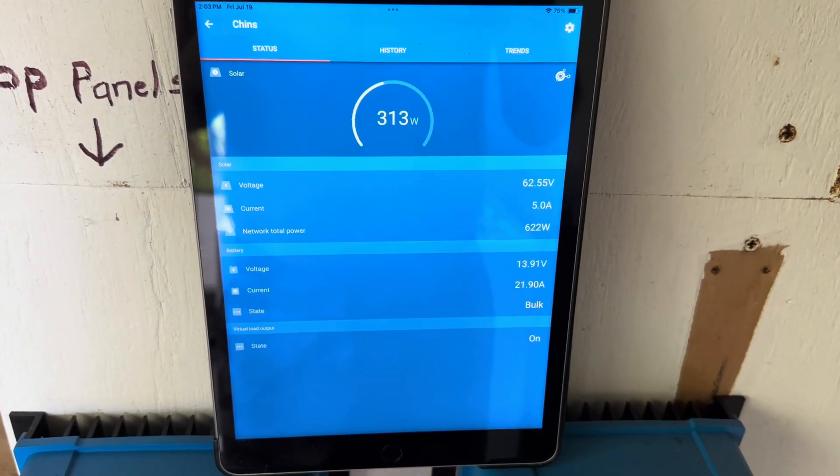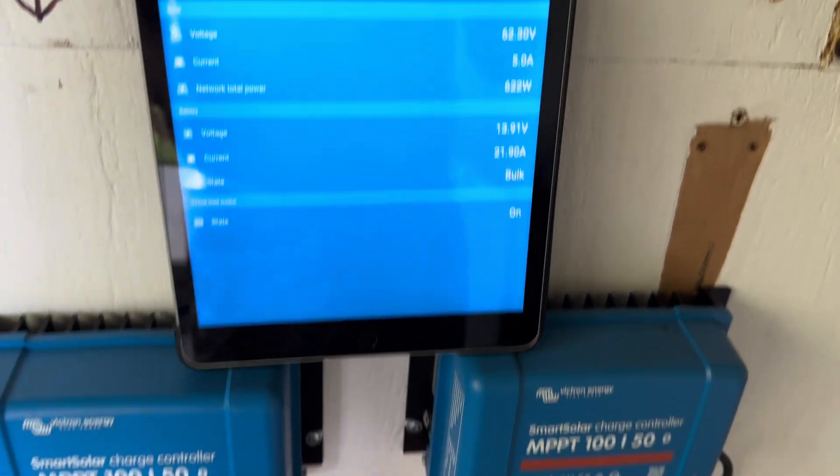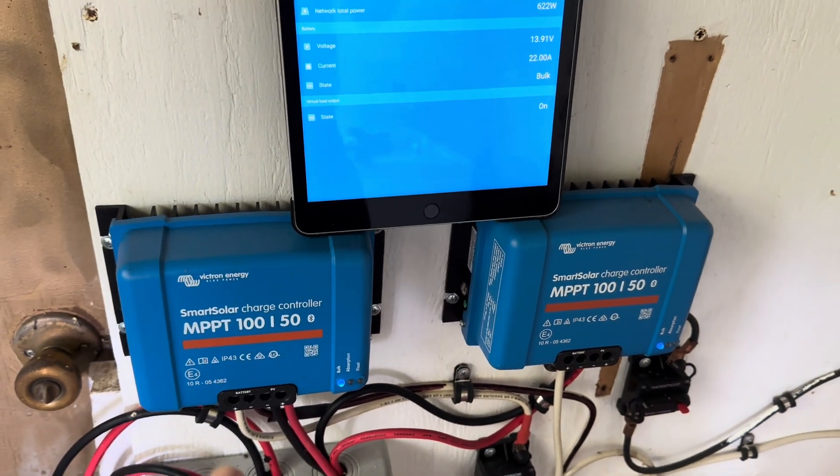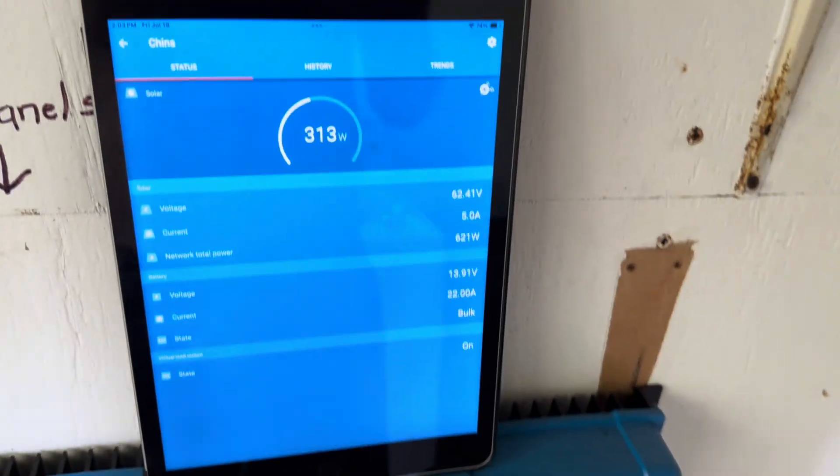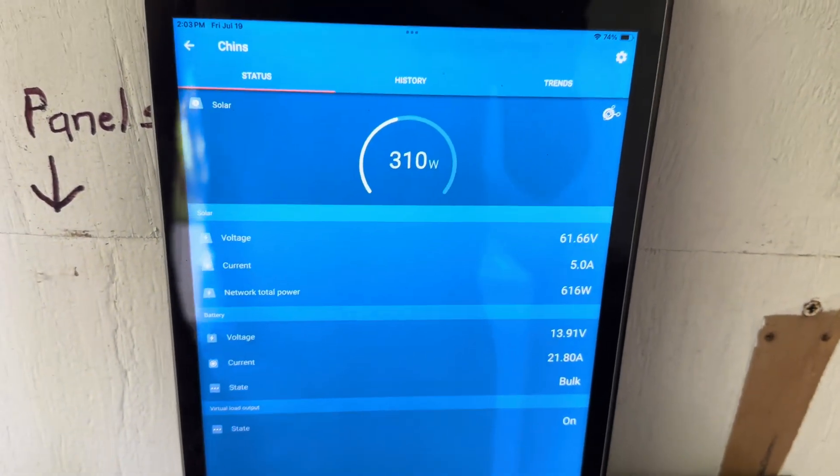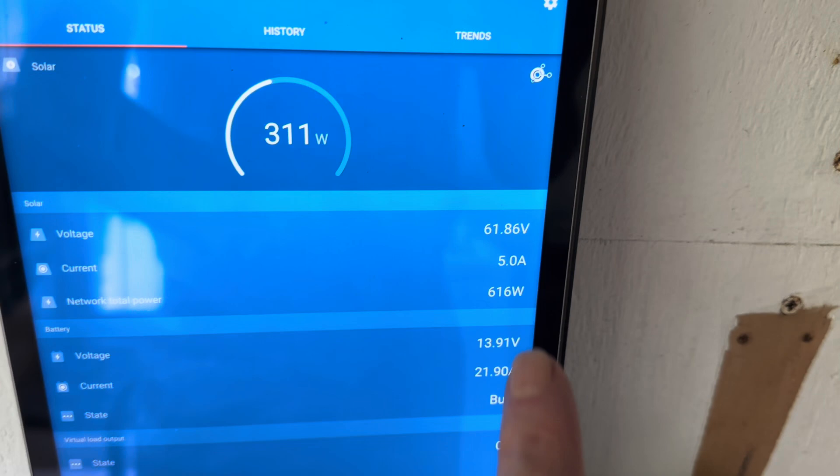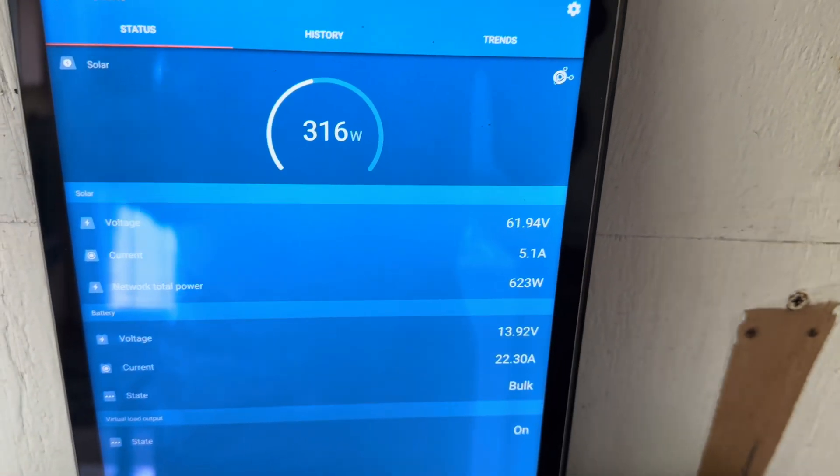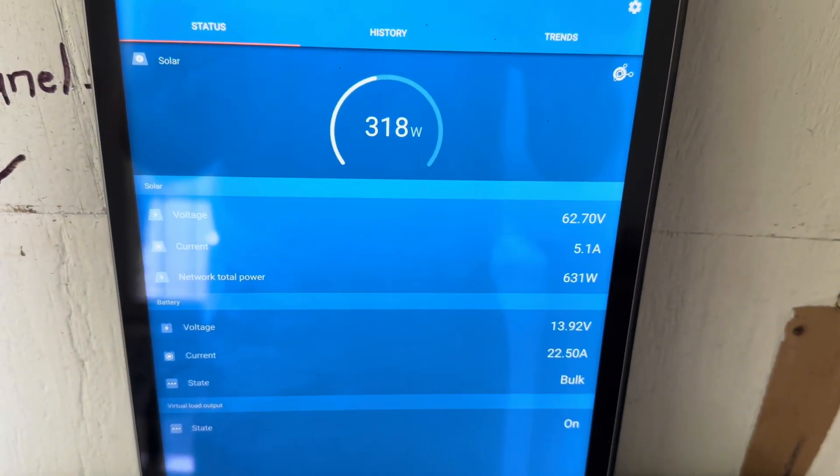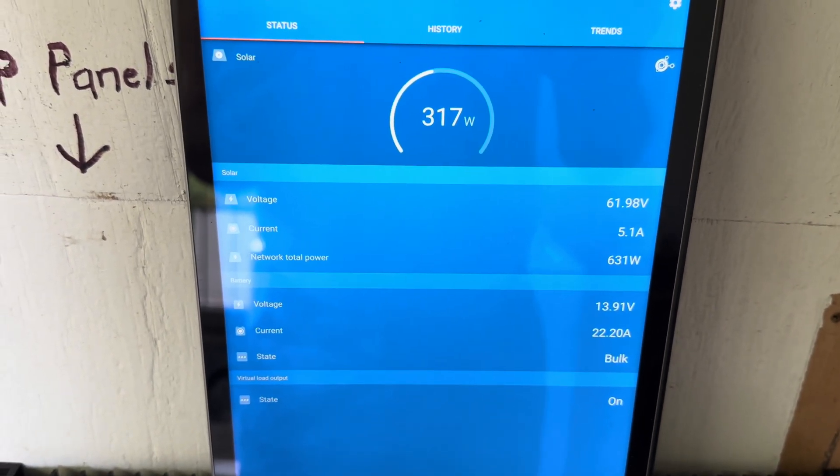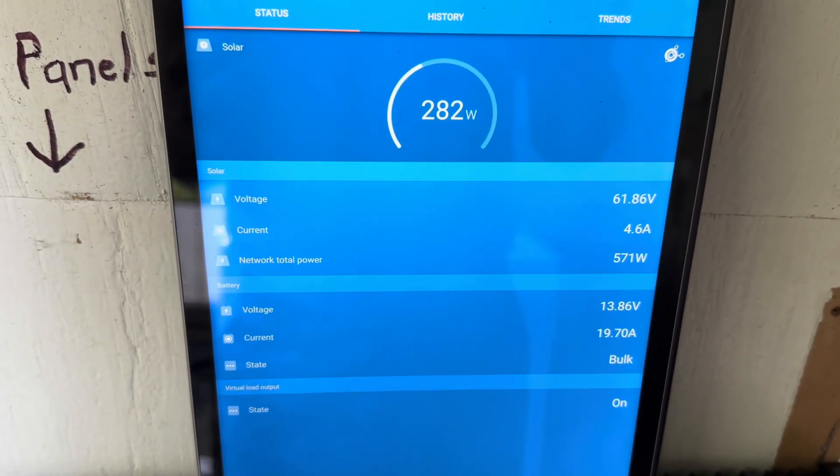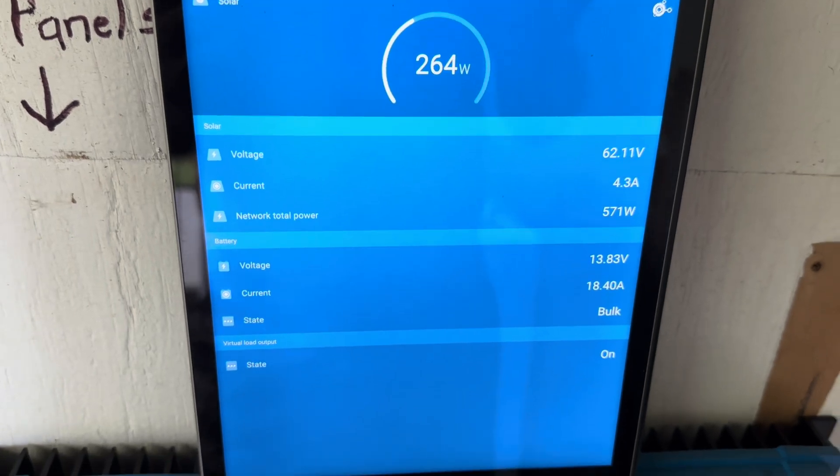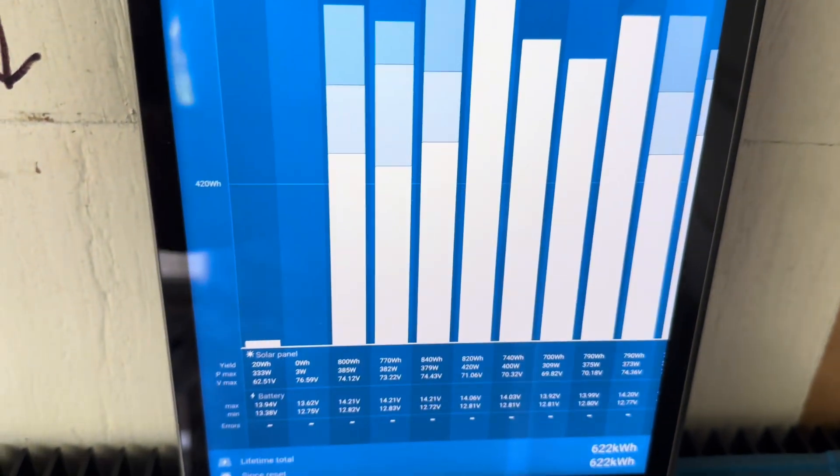And right now it's only been, you know, just a few minutes since I reset this controller here, and it's doing fine now. 300 and some watts coming in, the voltage looks good, 62, 63 volts coming in off the array.